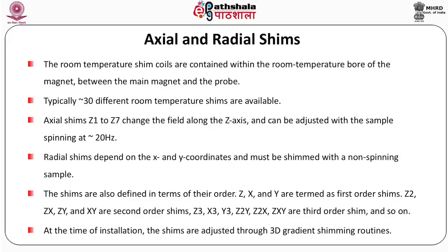There are axial and radial shims. The room temperature shim coils are contained within the room temperature bore of the magnet between the main magnet and the probe. Typically 30 different room temperature shims are available. Axial shims Z1 to Z7 change the field along the Z axis and can be adjusted with the sample spinning at approximately 20 Hz. Radial shims depend on the X and Y coordinates and must be shimmed with a non-spinning sample. Shims are also defined by their order: Z, X, and Y are first order shims; Z-squared, ZX, ZY, and XY are second order shims; and Z3, X3, Y3, Z2Y, Z2X, ZXY and so on are third order shims. At the time of installation, the shims are adjusted through 3D gradient shimming routines.